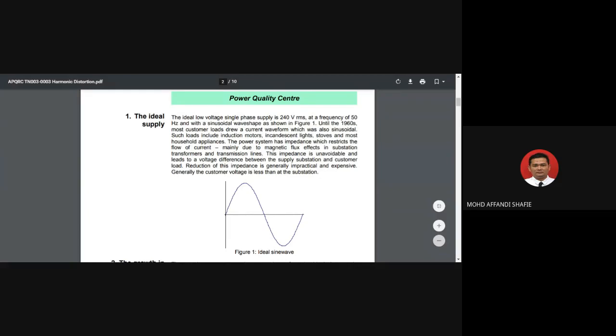Such loads include induction motors, incandescent lights, stoves, and most household appliances. The power system has impedance which restricts the flow of current, mainly due to the magnetic flux effect in substations, transformers, and transmission lines. The impedance is unavoidable and leads to a voltage difference between the supply substation and the customer load. Reduction of this impedance is generally impractical and expensive. Generally, the customer voltage is less than at the substation. That just explains the impedance of the power system.